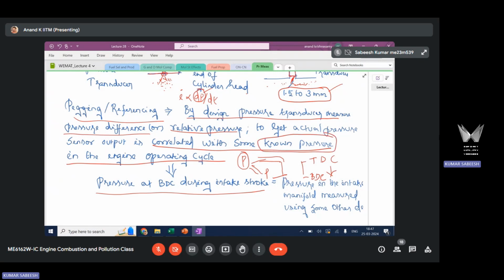You are actually getting the sensor output adjusted for a known pressure value. The known pressure value is the pressure in the cylinder when the piston is at bottom dead center, that is, at the start of compression stroke or end of intake stroke. You are adjusting the sensor output with this known value. By doing this, you are getting the actual value. This process is called the referencing or pegging process. So you are adjusting the output from the pressure sensor with some known pressure value. The known pressure value is the pressure in the intake manifold measured with some other equipment.